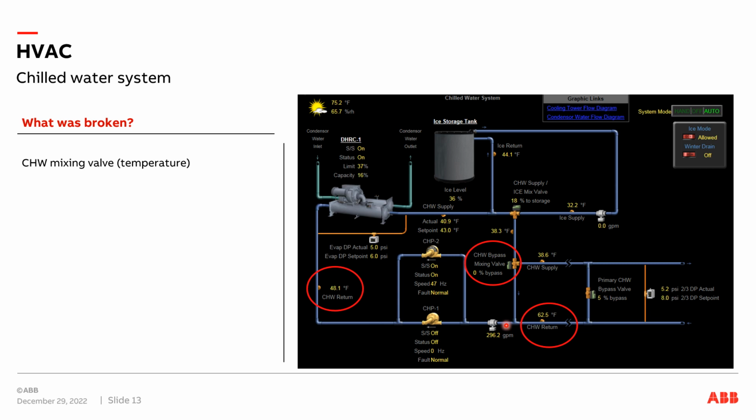So again, I took a screenshot of this to create this presentation. I let our facilities folks know, yeah, we've got a problem. They looked at it and were able to get it corrected. That just shows the importance of checking on your graphics every once in a while, just seeing what's going on. But you have to understand how the system is supposed to operate in the first place in order to know when there's a problem.